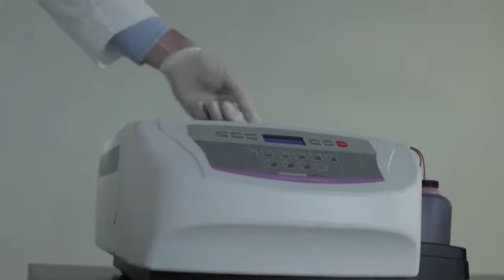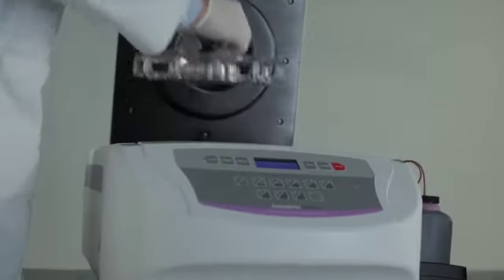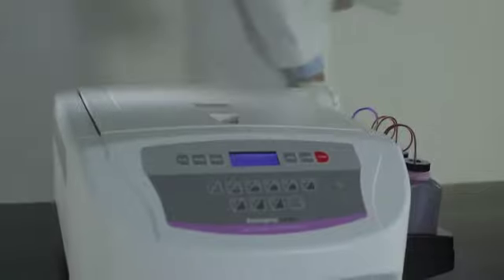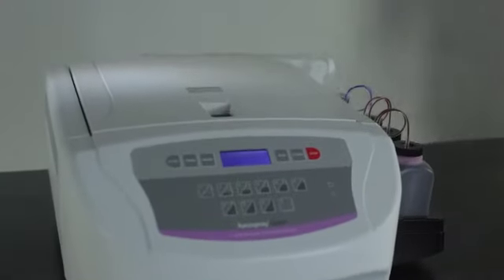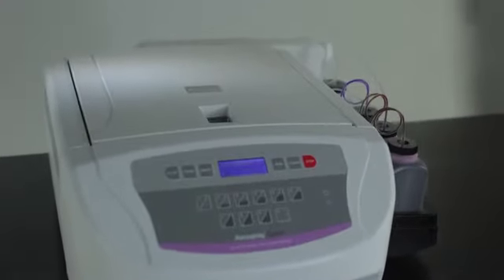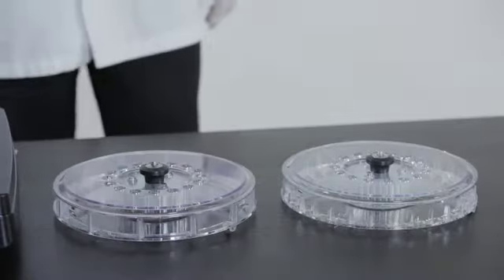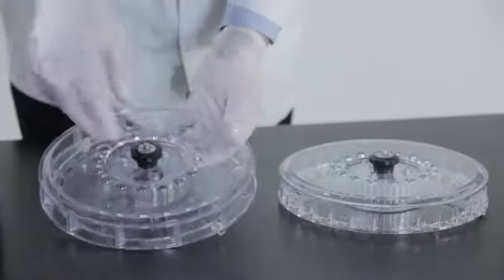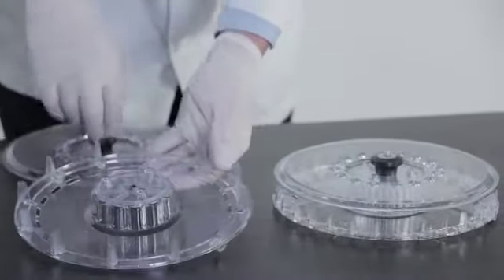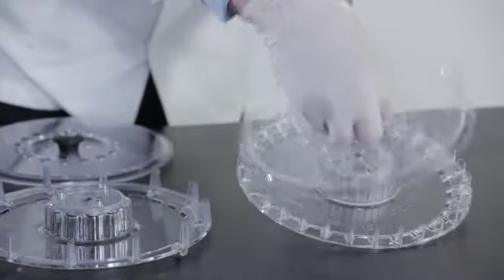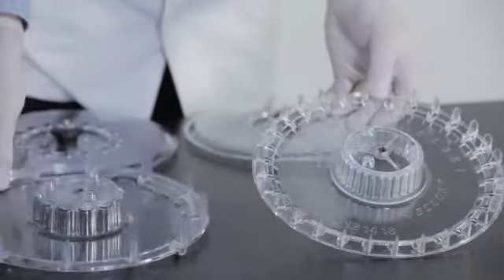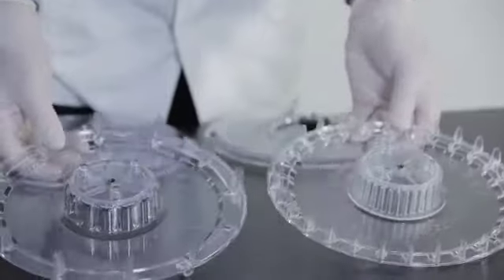The Aerospray Gram stainer performs a traditional gram stain. The stainer has 5 reagents and 6 nozzles. The D reagent is deionized or distilled water and is sprayed from 2 of the 6 nozzles. The gram stainer uses either a 12-slide carousel or a 30-slide carousel. The stainer automatically recognizes the size of the carousel, so no programming is needed.